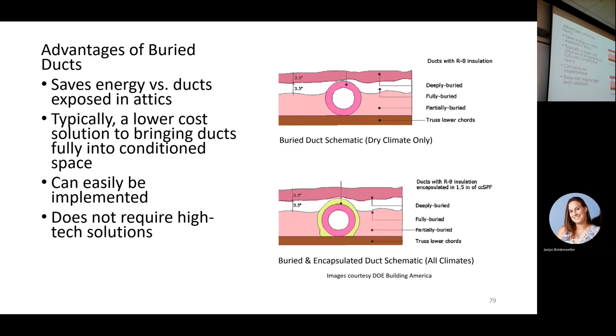If you're in a humid climate, they recommend you encapsulate the duct with spray foam, so spray an inch on the whole thing. And that is because in humid climates, it's hard to keep the vapor barrier intact. It gets snagged, it gets ripped or torn, and then we got the moisture problems with it. It's going to be a little bit expensive, but over the life of the house, how much money do you save if you have a well-insulated, airtight duct? The other thing the spray foam does is it seals the duct completely. How much duct leakage do you want in your house? How much of the air that you just paid for heat or cool you want to leak out in your attic and be gone? Every time you leak 100 CFM out of your attic, 100 CFM has to leak back into the house to replace it. And then you have to heat or cool it.